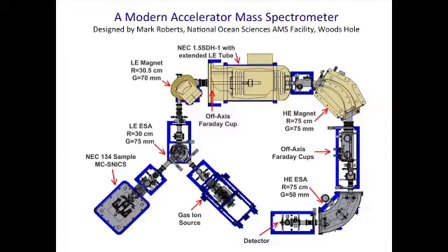In the middle of the accelerator is a terminal that's at about plus two and a half million volts. So an ion comes in here, it gets strongly accelerated, and now it has a translational kinetic energy of about two and a half million electron volts when it gets there. And then — surprise — here's some argon. You maintain in the middle of the accelerator a fog of argon gas at about 10 to the minus 4 torr. So here comes this negative CH minus molecular ion floating along and all of a sudden it's got to find its way through this argon.